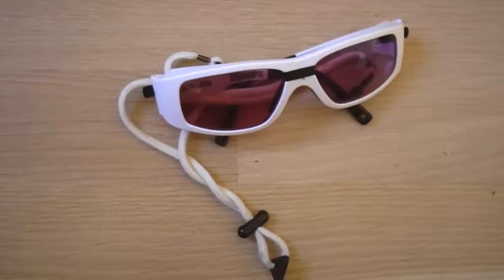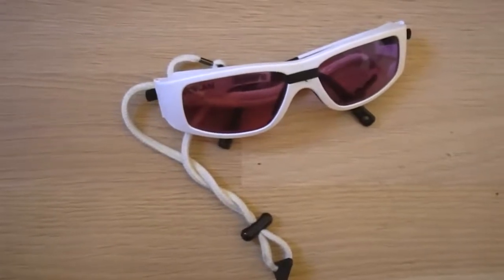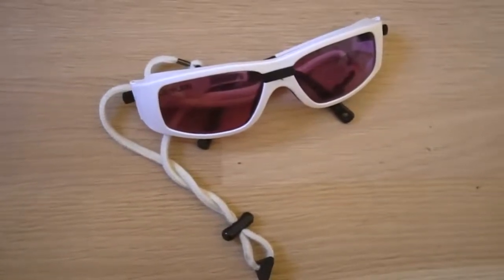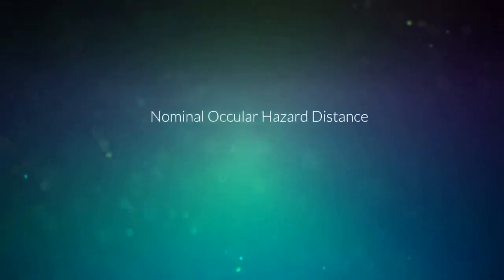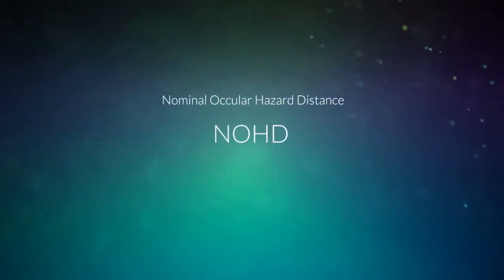Both the filter and the goggle frame are considered in the calculation, and since the worst-case scenario conditions are used, this does not allow for reduced eyewear protection outside of the nominal ocular hazard distance, or NOHD.